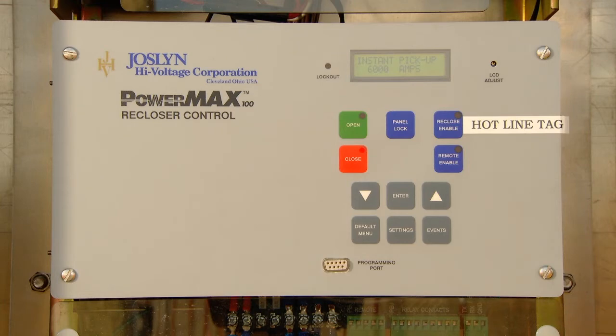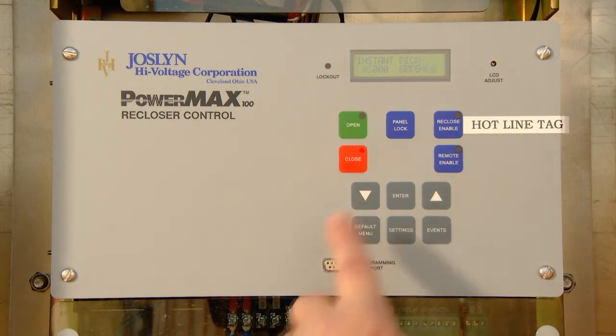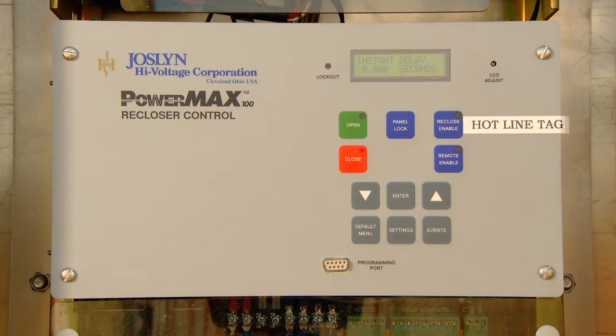This particular unit is rated for 6,000 amps maximum current flow. And finally, press again to display instantaneous delay. This feature allows you to program a delay if so desired. The settings past this are not really of interest to a lineman.